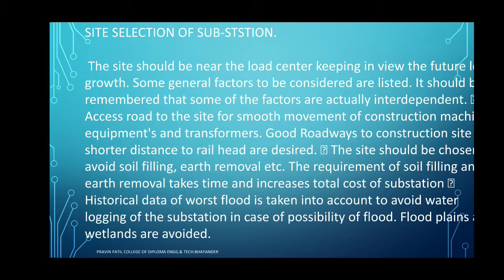Then we have to select proper land for the electrical substation. Some general factors to be considered to install the substation: it should be near the load center. Then the substation should allow smooth movement of construction machinery and electrical equipment, with a good roadway, as it is always connected to the road or the rail for the transportation of electrical equipment. The site selected should avoid soil filling and earth removal. That is also an important point for selection of the site.